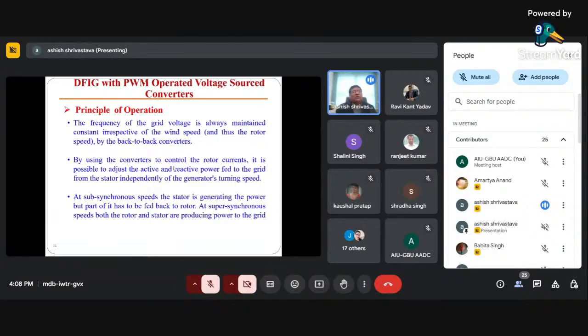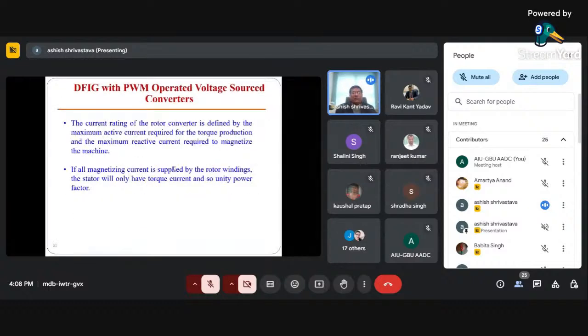And at sub-synchronous speed, which is lower than the synchronous speed, the stator is generating the power, but part of it has to be fed back to the rotor. So that means you can feed back the power to the rotor as per the requirement. And at super synchronous speed, both rotor and stator are producing power to the grid. So at super synchronous speed, we are feeding full power to the grid, and at sub-synchronous speed, some power from the grid is fed back to the rotor side for better power quality control and frequency control.